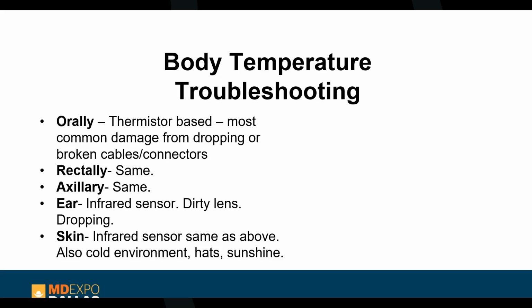Orally, thermistor based, this is troubleshooting for body temperature. Most commonly it's dropped or damaged from dropping. It usually has a cable that connects to the main box. The cables get damaged and the connectors get damaged. That's usually the most common, or they drop the entire box and it breaks. I know no one ever drops equipment in the hospital, but somehow it magically happens, but no one did it.